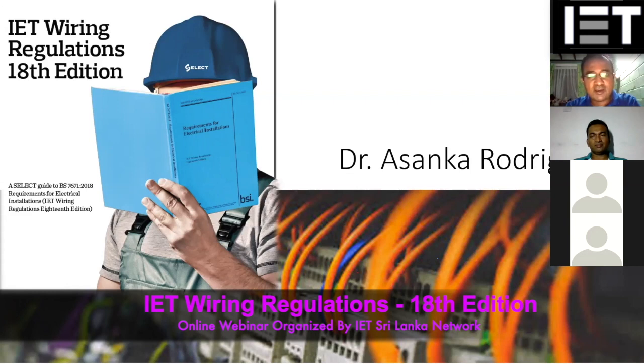Okay, thank you, Doctor. Next question is, are there any special considerations to be met if the lightning earth and equipment earth are combined? That is the same thing, I think. As I said, you have to have these two combined, because you have to have the SPD as well as connect the equipotential bonding. Sometimes if you do not select the correct SPD, then there can be a problem. Otherwise, all the standards recommend going with equipotential bonding with the SPD connection. So for all the data connections and all the power connections, you can install SPDs and connect them to the equipotential bonding, and if you maintain your electrical installation like that, there won't be any problem.